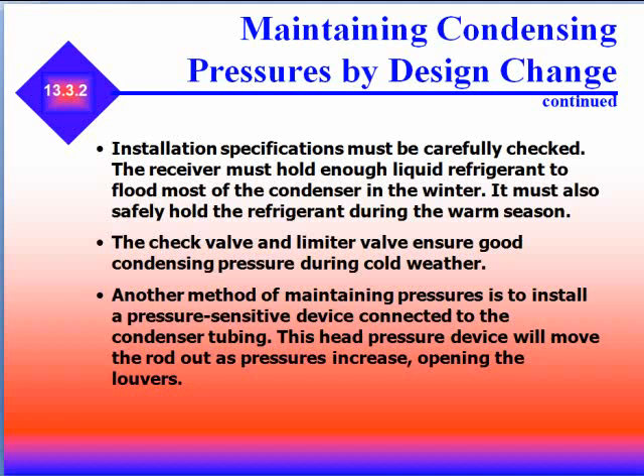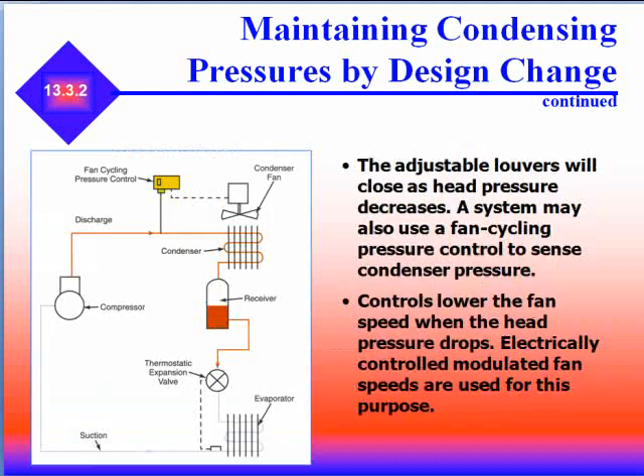Another method of maintaining pressure is to install a pressure-sensitive device connected to the condenser tubing. This head pressure device moves a rod out as pressure increases, opening the louvers. The adjustable louvers close as pressure decreases. A system may also use a fan cycling pressure control to sense condenser pressure, lowering fan speed when head pressure drops. Electronically controlled modulated fan speeds are also used for this purpose.